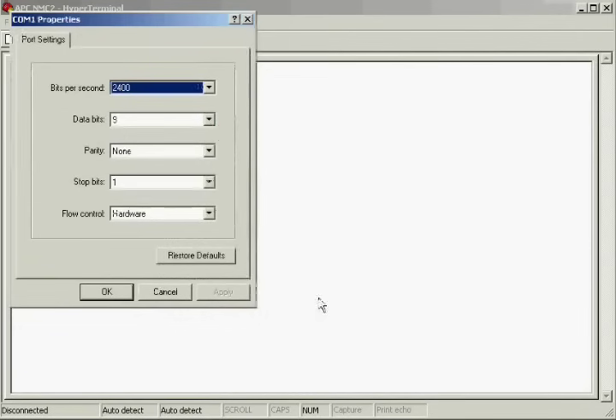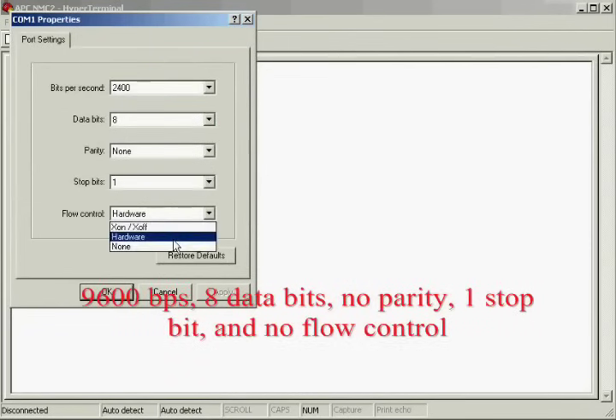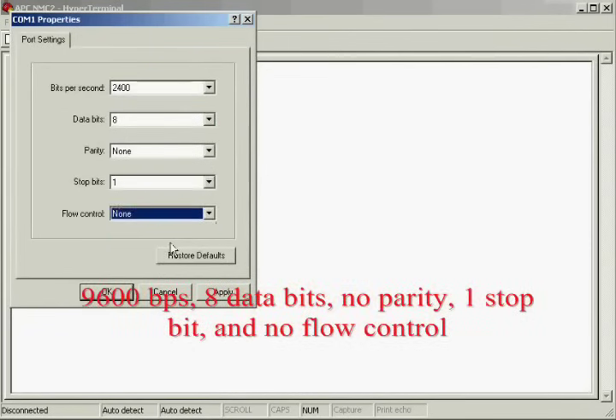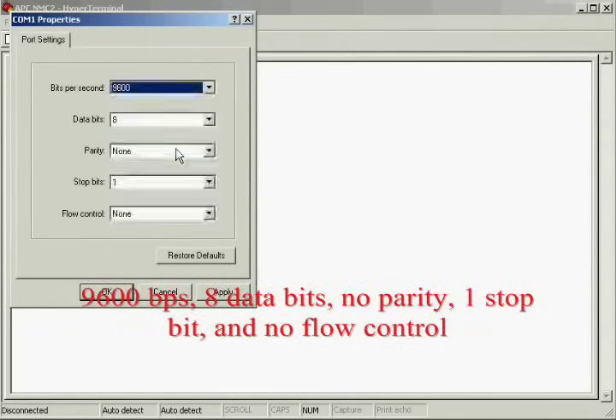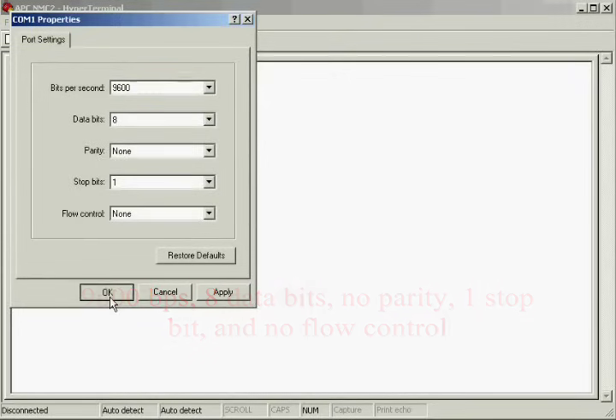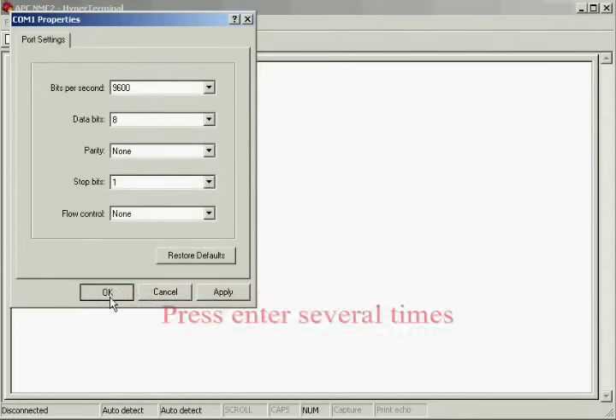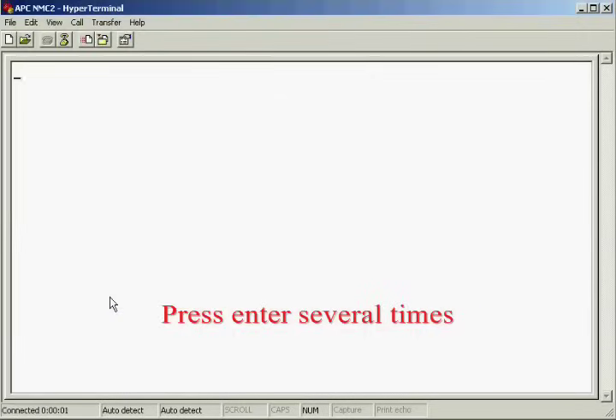Then, select the applicable COM port. The port settings are 9600, 8 data bits, none for parity, 1 stop bit, and none for flow control.